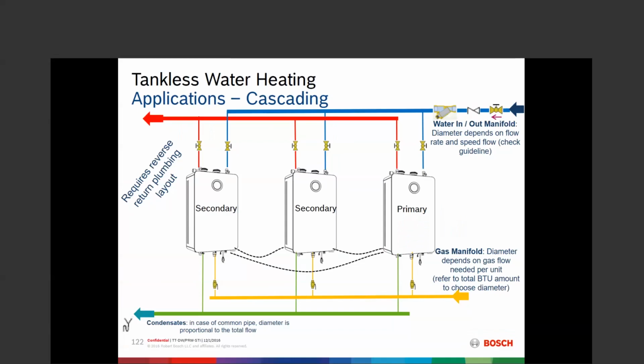We also have the capability to do cascading. So if one heater can't get it done, we can let you put up to 24 of these in a cascade. We want to see that in a reverse return situation, so the pressure through each of the units is the same. We want to make sure that that's going to happen. We want to make sure that your gas line sizing and your gas meter sizing is adequate for all the units. Then they work as a bank, and as they work as a bank, they actually have a lead lag function. So after the primary unit fires for 100 hours, it designates the next one as primary, and so on and so forth out through the entire 24 or up to 24 units.